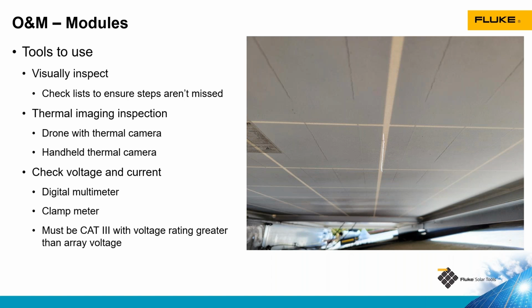You'll need a category 3 rated tool with a voltage rating higher than what you're testing at. If you're on the AC side of the system, depending on how it's interconnected to either the electrical system in the building or the utility, it may be a category 3 or category 4 environment. Again, we need to make sure that we've got a voltage rating above the voltage at which we will be testing.